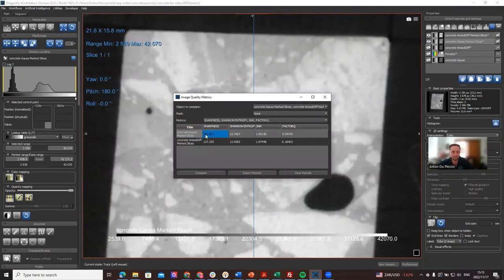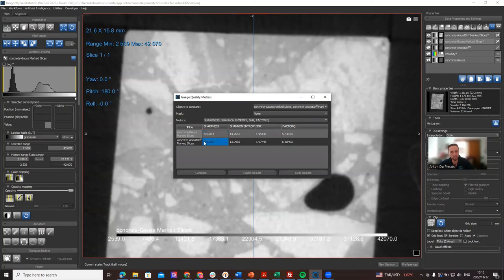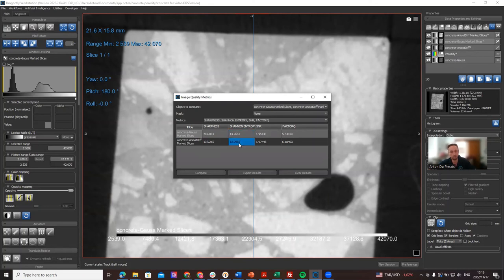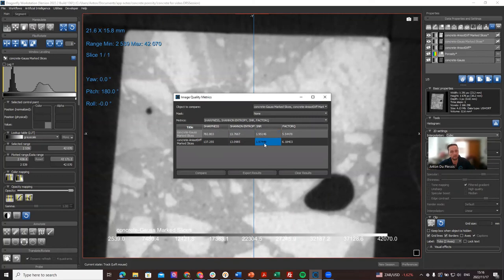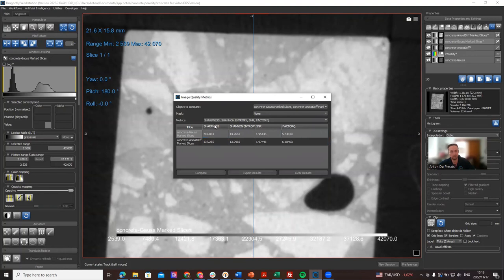We can calculate different image quality metrics. What we can see here is that the original data had a 782 sharpness value where the denoised one had only 137, so this is much lower as we've seen it was blurred out. There's also Shannon entropy which has not changed that much, regular signal to noise ratio which is slightly higher in the denoised one, and a Q factor calculation which is slightly higher in the denoised one, but the sharpness in this example is clearly different.